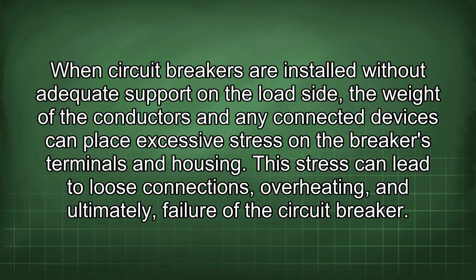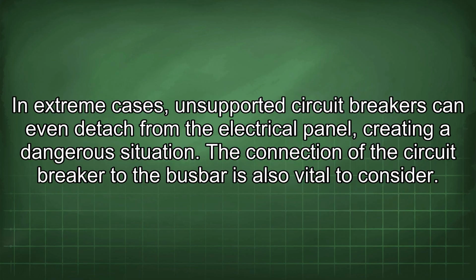When circuit breakers are installed without adequate support on the load side, the weight of the conductors and any connected devices can place excessive stress on the breaker's terminals and housing. This stress can lead to loose connections, overheating, and ultimately, failure of the circuit breaker. In extreme cases, unsupported circuit breakers can even detach from the electrical panel, creating a dangerous situation.